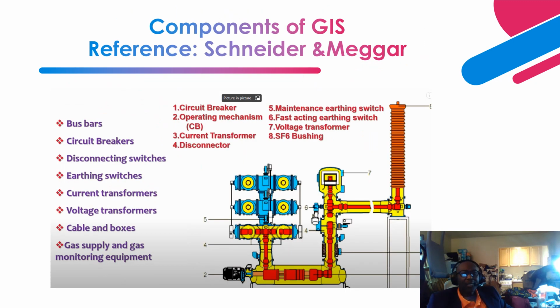Okay. So similarly, we have basically on the line side, right, we have disconnect switches and earthing switches, and the CTs are located over here, right, and this is the VT that is located over here. Next, I think I went through this scheme on the previous slide. Okay, so this one is an apparatus bushing, right, called an SF6 bushing. It is filled with SF6. From this side, we have the overhead line, the air side, right? The air side is this, and this is the SF6 side. Okay, so this is basically a bus, right? That is inside an enclosure. The enclosure is all filled with SF6.